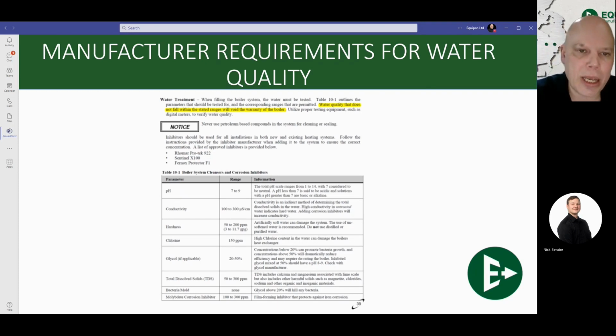The only way to balance pH in demineralized water is by using a chemical stabilizer, such as the Fernox F1 Protector listed here in this manual. These chemical compounds have buffering agents in them that are going to buffer the pH to about neutral, which is about 7. The other thing these will do is that if there are any particles in the water, any TDS floating around, it will suspend them. It will not let them stick to any of the hot areas. It's going to keep those magnesium and calcium particles moving through the water and not let them stick to anything and become larger deposits. So that's really where chemical compounds come in, which makes them so effective as an addition to demineralized water.